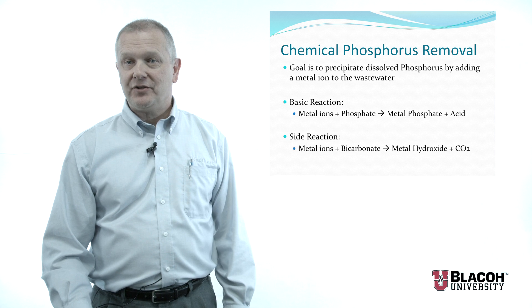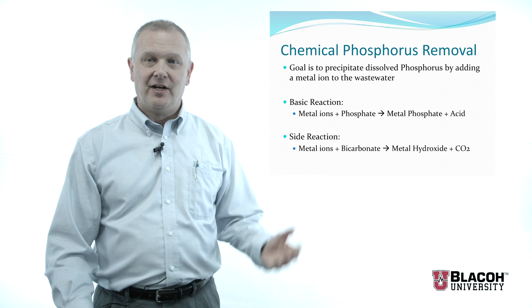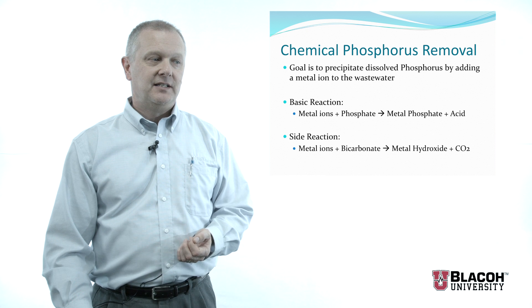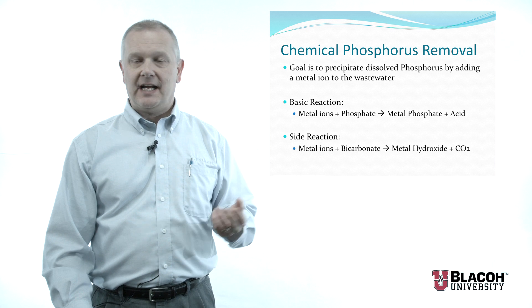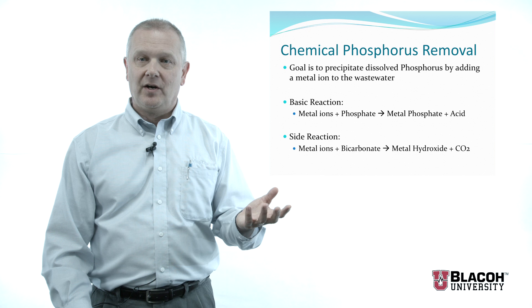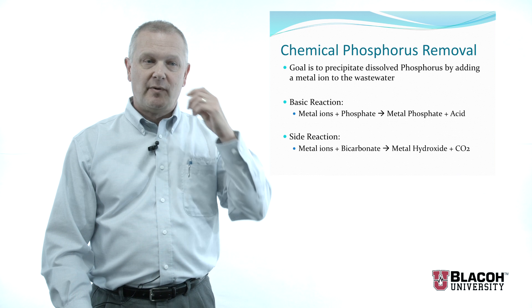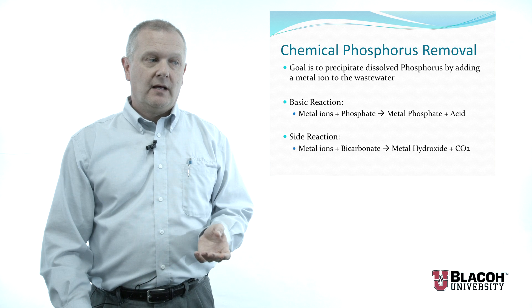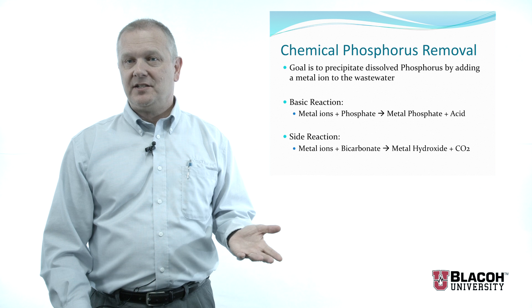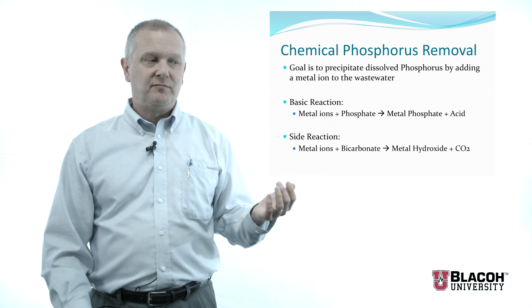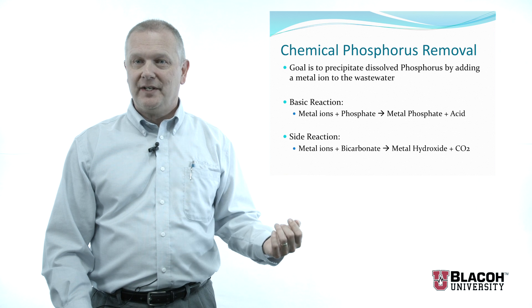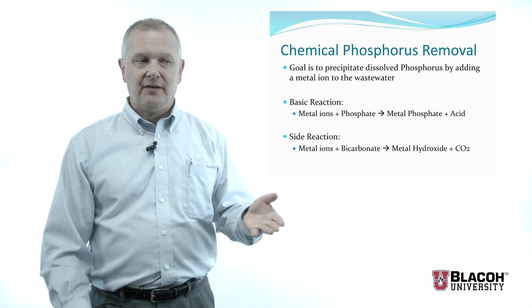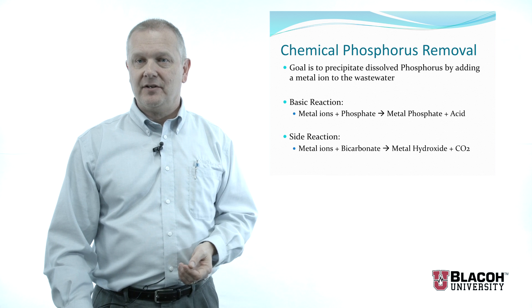Unfortunately, we also get a side reaction: the metal ions we add also react with bicarbonate or hardness in the water to form a metal hydroxide. This is not a problem from a process standpoint, but it's a problem for chemical dosing because you need more chemical since some of it is used up reacting with the hardness in the water.